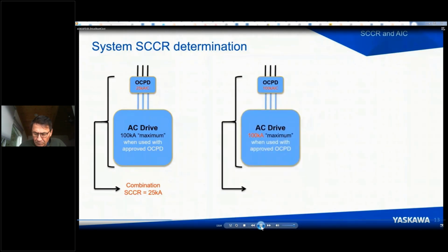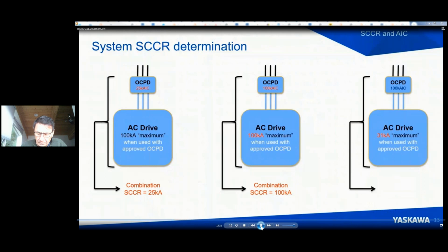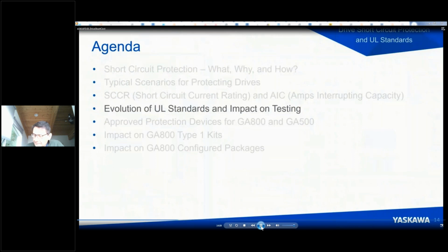Let's look at a situation where they equal each other. Both the overcurrent protective device and the drive are rated at 100,000 amps. In that case, the combination is rated at 100,000 amps. Now let's look at the opposite, where the overcurrent protective device has an interrupting capability of 100,000 amps, but the drive only has a capability of 31,000 amps. In this case, the combination is 31,000 amps. Pretty easy to remember, right? It's just the lesser of the two rated devices. There are cases where there are combination ratings, but we're not really discussing those today, combination ratings for components, that is. Next, let's move on to the evolution of the UL standards and how that has impacted testing.